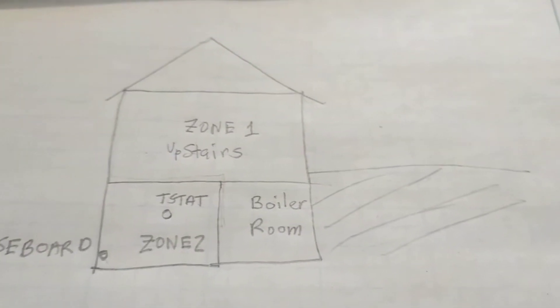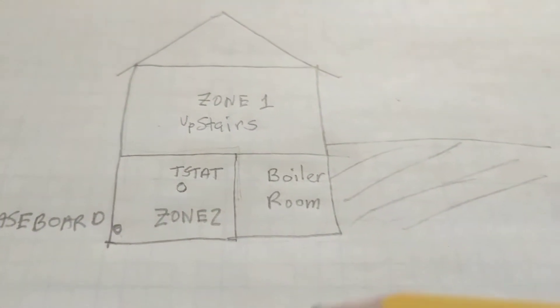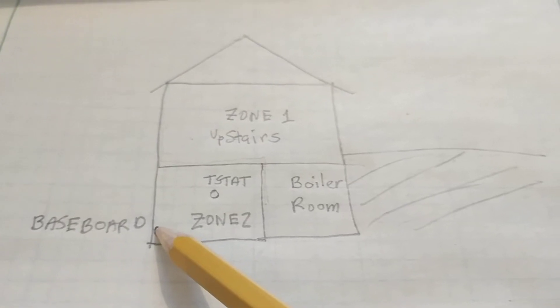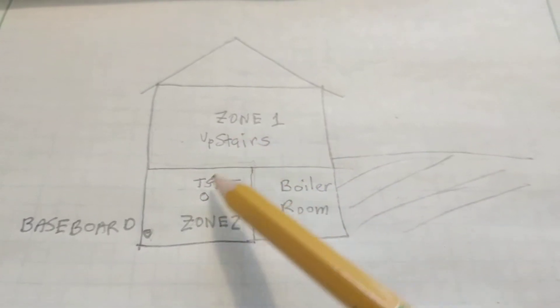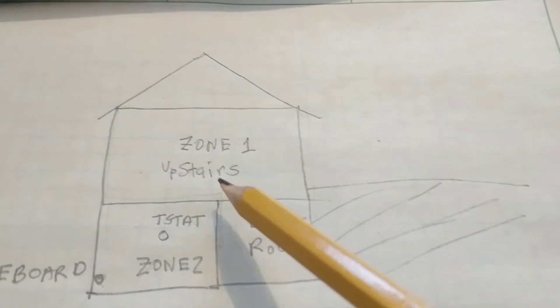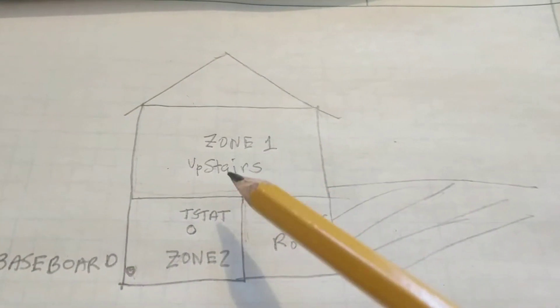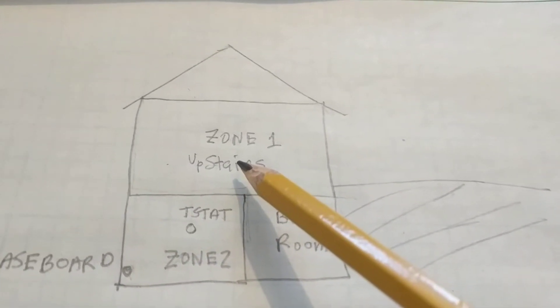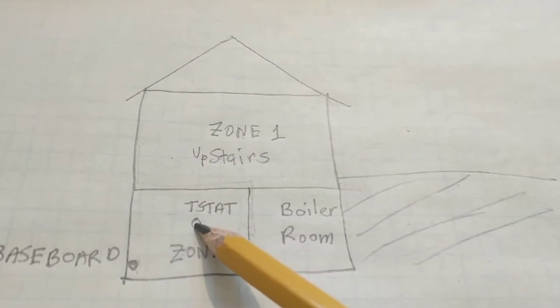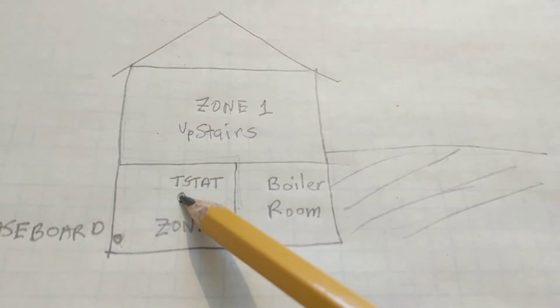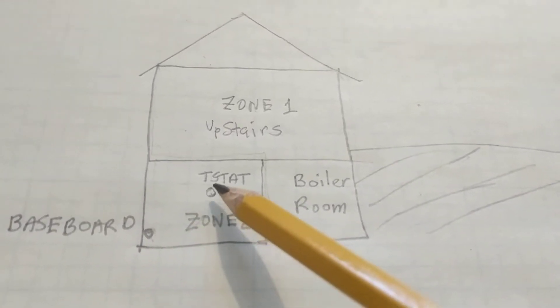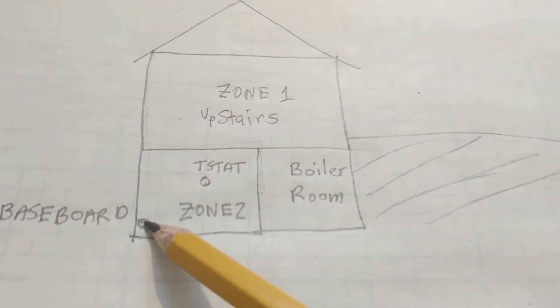This video describes a potential — actually an actual — freeze-up at a baseboard hydronic heater in a two-zone system. The question is: what was the failure mechanism? In this case, when the freeze-up took place, the upstairs zone was set to 62 degrees and the downstairs zone was set to 45 degrees — 13 degrees above freezing. How could the baseboard freeze if the zone is being kept at 45 degrees?